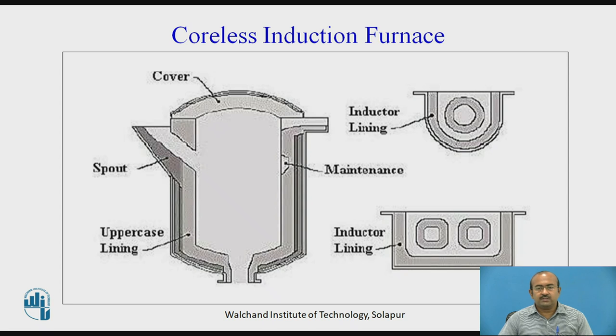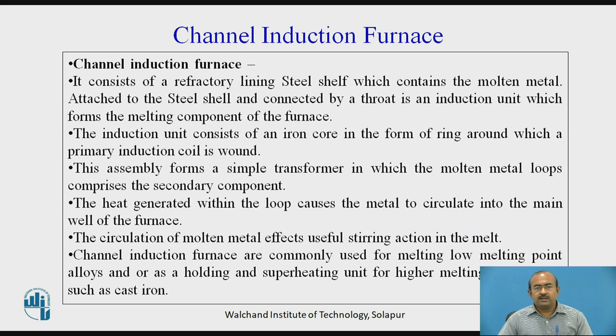The coreless induction furnace parts are shown individually. The channel induction furnace consists of a refractory-lined steel shell containing the molten metal. Connected to the shell by a throat is an induction unit that forms the melting component. The induction unit consists of an iron core in the form of a ring around which a primary induction coil is wound, forming a simple transformer in which the molten metal loop acts as the secondary component. Heat generated within the loop causes the metal to circulate into the main well, producing a useful stirring action in the melt.